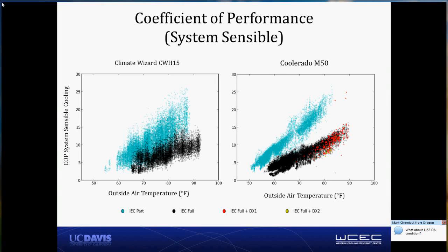I'll also admit that there was a little bit of a failure in the way that we controlled these systems, which we only recently found, which wasn't allowing the compressors to turn on for all of the Climate Wizard systems, except after the second call for cooling persisted for a very long time. And typically, by that point in time, the load in those zones had been covered by one of the other systems.